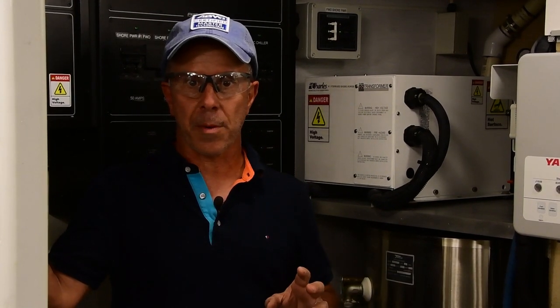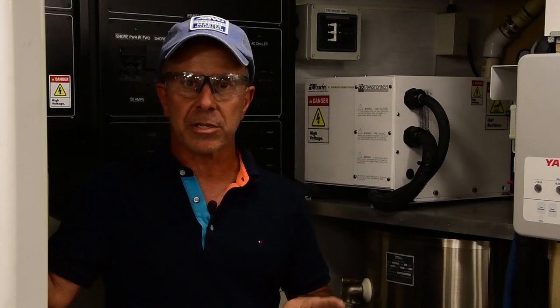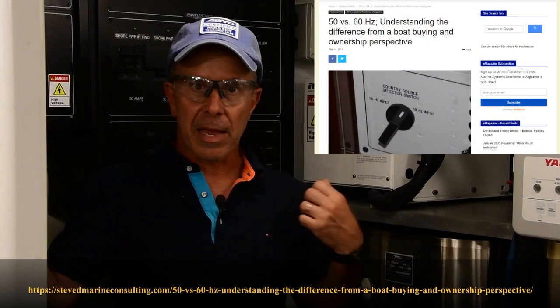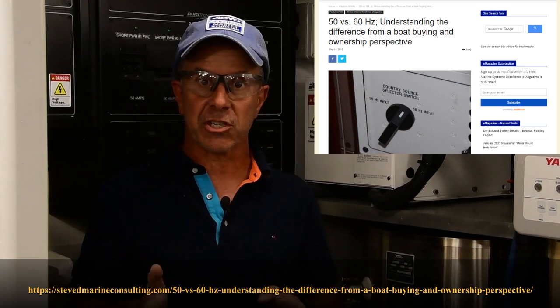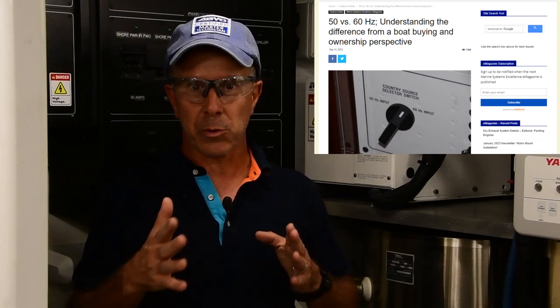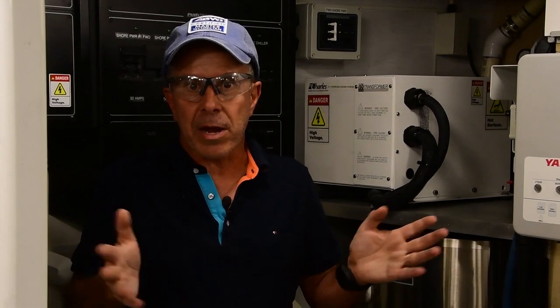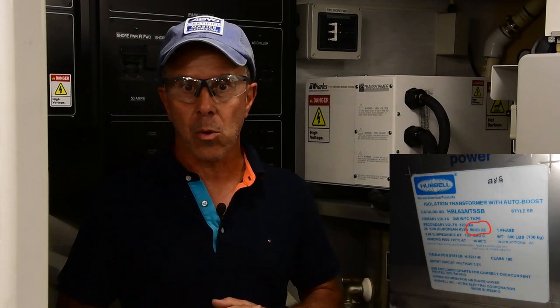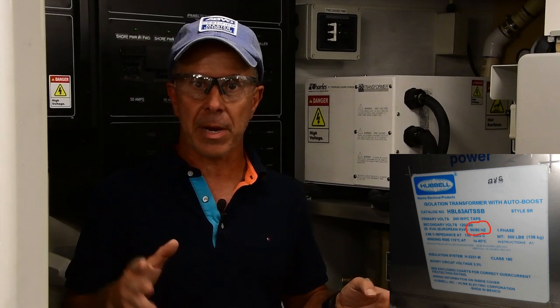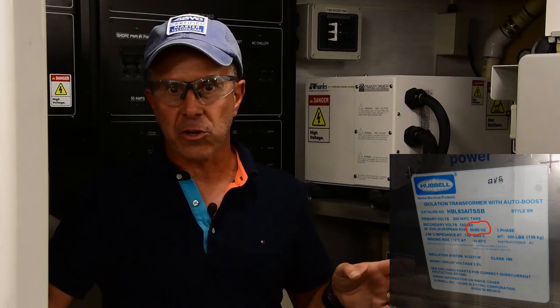Now, if you operate your vessel in North America, for instance, then the shore power is going to be what we call 60 hertz. That's the frequency of the shore power. But if you travel to other parts of the world, to Europe, to Australia, some South American countries, well, there the frequency will be 50 hertz. If your transformer is not designed to accept 50 or 60 hertz, if you plug a 60 hertz transformer into a 50 hertz shore power, even if the voltage is correct, the transformer will not work. It will not pass the power. So my recommendation is any transformer that gets installed, any 240 volt transformer that is, should be capable of operating on 50 or 60 hertz, because you really never know where the vessel may end up and what type of shore power environment it might end up in. You want it to be able to work on either 50 or 60 hertz.